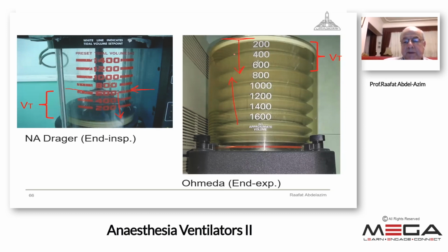Each of these ventilators will give the preset tidal volume, but the difference is that in the Ohmeda ventilator, the bellows is fully inflated at the end of expiration. At the end of inspiration, it is partially deflated according to the tidal volume. In the Draeger ventilator, it is partly inflated at the end of inspiration and fully deflated at the end of expiration. The video will make it more clear.